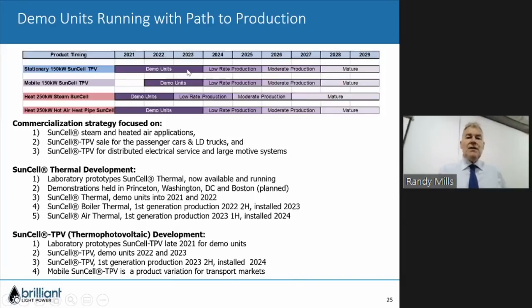The boiler application is ready to deploy now in pilot systems, and we're working with OEMs, particularly two of the best heat pipe manufacturers there are, to build components with heat pipes and heat transfer systems. A heat pipe is basically a closed pipe with an alkali metal that boils and carries an enormous amount of heat as it boils, compared to conduction and convection. It condenses and transfers heat extremely efficiently along the pipe's length, keeping it at a steady temperature. The heat fins receive that heat, we blow air through it, and we end up with variable temperature hot air, 100 to 500 degrees C. The component manufacturers will make that system for us as a turnkey add-on to our cell.